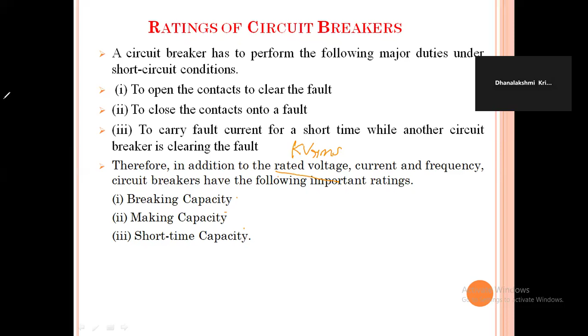We move to the following important ratings: breaking capacity, making capacity, and short time rating. First one is breaking capacity. The breaking capacity is expressed as the highest value of short circuit current that the breaker is capable of breaking under specified conditions of transient recovery voltage and power frequency voltage. It is expressed in kilo ampere RMS, at contact separation.